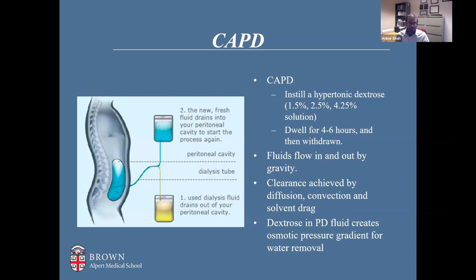With PD, there are 2 ways that PD can be prescribed. One would be automated PD, or APD or CCPD. The other would be manual PD, or CAPD. We will briefly discuss each of these. For CAPD, this is done manually. You use gravity to instill the dialysate and you use gravity to drain the dialysate. Typically, you will use a hypertonic dextrose solution. You'll let it dwell for 4 to 6 hours and then waste that solution. Over those 4 to 6 hours, it will become saturated with uremic toxins, with potassium, with all the milieu that we're trying to get rid of. We use gravity to let the fluids flow in and out.